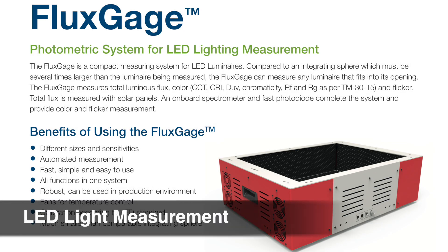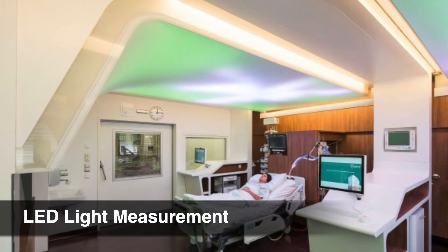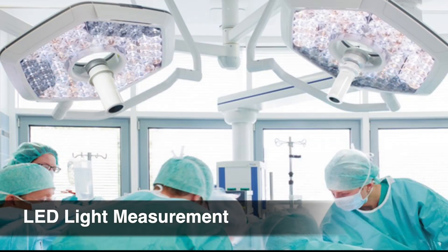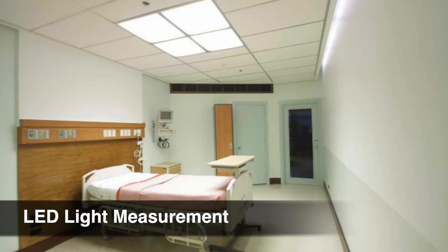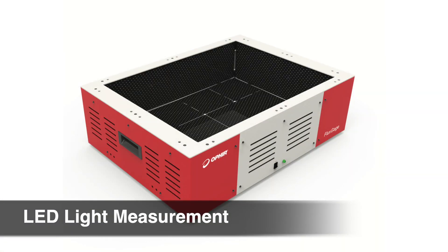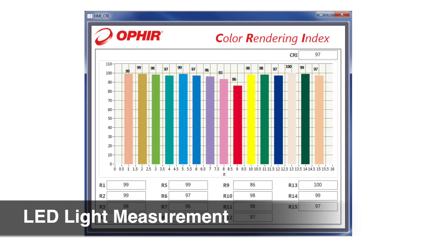In addition to measuring laser light, Ophir also developed a measurement device for LED luminaires used in operating rooms, anesthetic recovery rooms, or for daylight simulation. Lighting parameters of LED luminaires, as used for the well-being of patients as well as for the surgeons, can easily be adapted to specific needs, but they need to be consistent. Even slight tolerances can destroy the positive effect. FluxGage integrates everything to get your light right — it measures total luminous flux, color, and flicker.